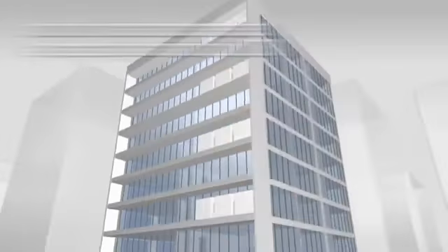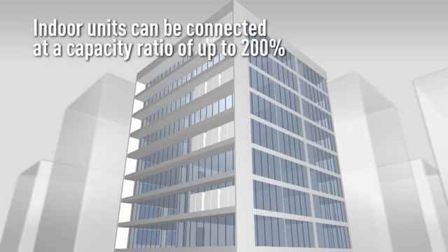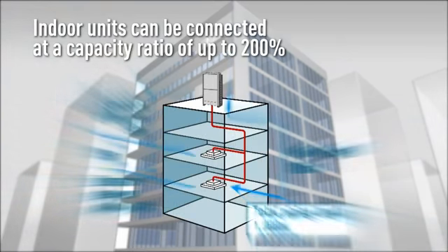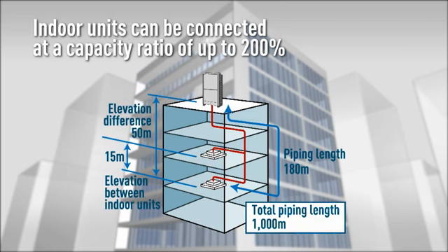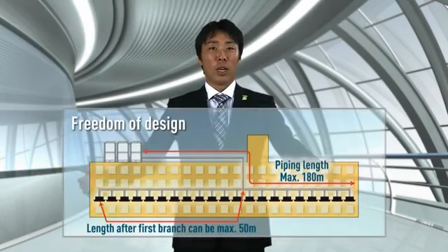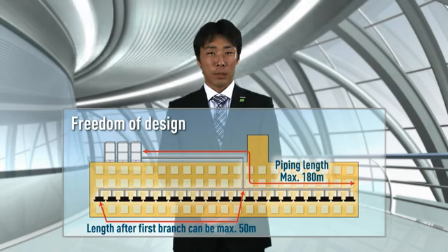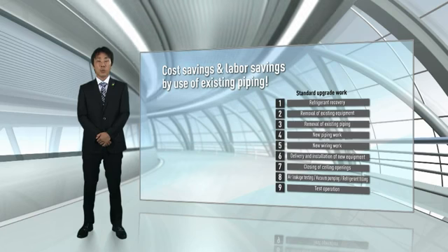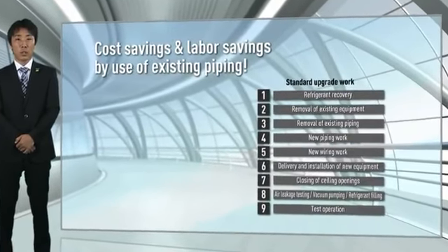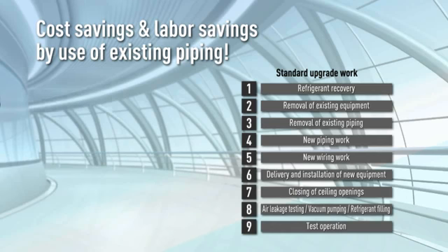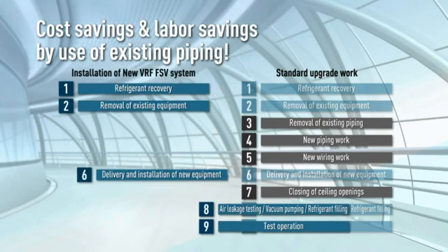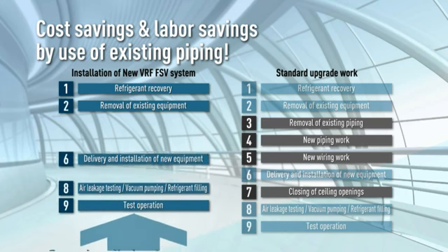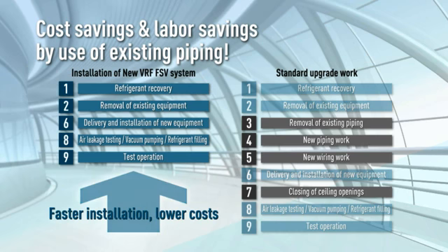Plus, the indoor units can be connected at a capacity ratio of up to 200% with a maximum 180-meter piping length, 50-meter elevation difference, and a 1,000-meter total piping length. Even for large-scale facilities that sprawl horizontally, this provides ample freedom of design. The system can use existing piping, so renovations are possible without the need to install new piping. In addition to eliminating the expense of new piping, it reduces the costs involved in removing and disposing of existing piping, and less waste material means much less environmental impact.